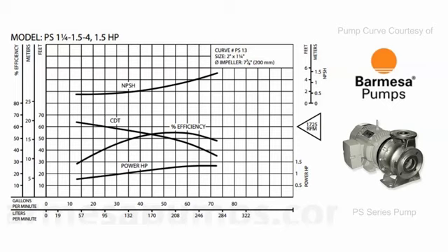And what we can see here is once we get into the 1 horsepower, which is this line here, the 1 horsepower essentially can handle from this point of the curve to this point of the curve without any problems, and that would be without overloading the motor. So essentially, when you look at the performance curve, that says that we can operate at 1 horsepower to about 30 gallons a minute roughly.